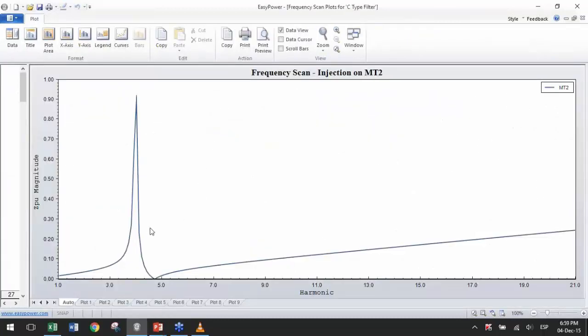Now I get two important points. This spike here is the resonance, which is a point that I want to avoid, completely avoid. And this is the anti-resonance, which is the point that my filter is tuned to. This is a fifth harmonic filter, and the anti-resonance is a little lower to avoid drawing much current, and there are other factors which I will not discuss in this webinar. Now, you might see that the resonance doesn't disappear. It's still there, and it's a resonant point for the system, but it's not at the fifth harmonic.